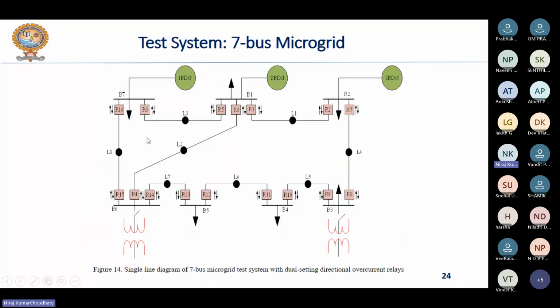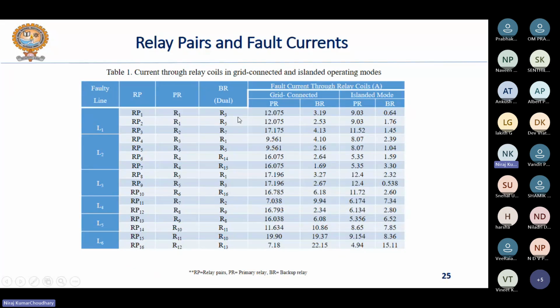Actually, you need to calculate the current flowing through the relay coil, because the fault current flowing through a particular line or feeder will be very high. That's why every relay coil is connected across the CT secondary, current transformer secondary, and depending upon the CT ratio, adjusting the CT ratio, you can modify the current that may be allowed to flow through any relay coil, right? So we have calculated the fault current through the relay coils in both the grid connected mode of operation and islanded mode of operation.